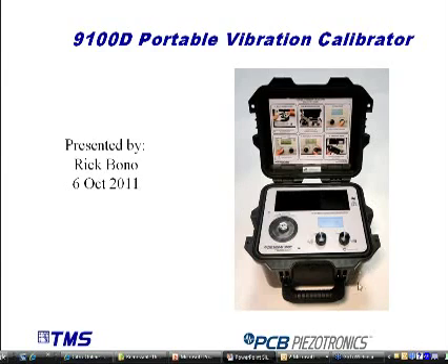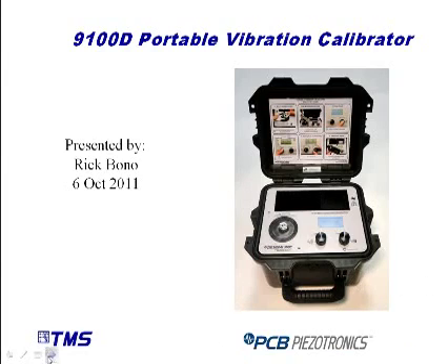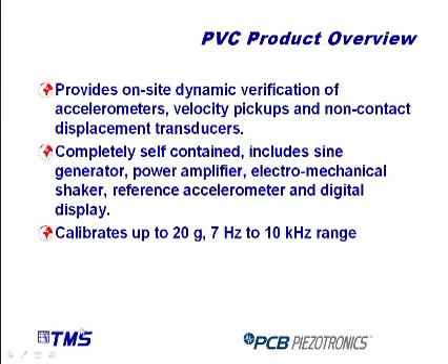What's it doing? The portable vibration calibrator is designed to provide on-site, in-the-field dynamic verification of accelerometers, velocity pickups, and proximity probes. The unit's completely self-contained, very small and portable, easy to get out into the field.